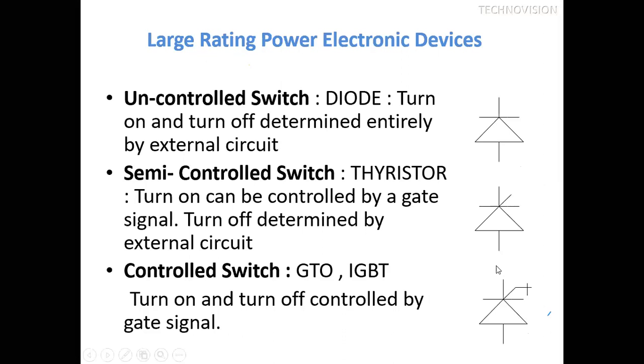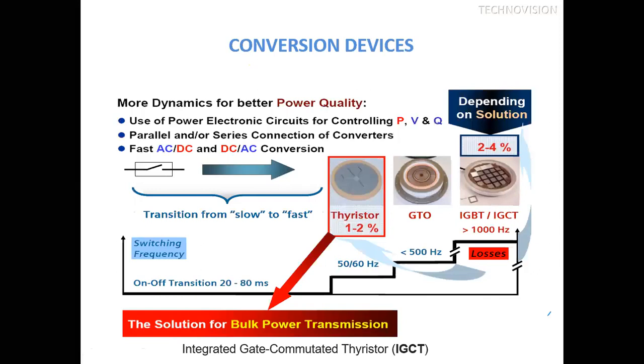So time is very less, so we'll try to cover it. This is the comparison of devices. Thyristors are operated at 50 to 60 hertz. GTOs can be operated at frequencies less than 500 hertz, and IGBTs or IGCTs, that is integrated gate commutated thyristors, can be operated at a frequency of 1000 hertz or sometimes 2000 or 3000 hertz also.